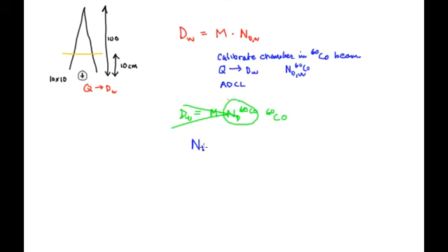So what you really need is to take this NDW calibration factor in cobalt 60 and convert it into some other calibration factor, ND dose in water, NDW, in your LINAC beam. To do that, you apply this KQ factor. That's a quality conversion factor.